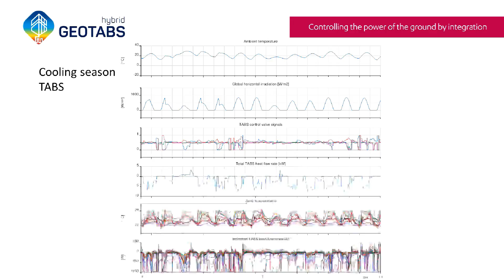Another thing that we observed at some point, but I didn't illustrate it here, is that the actual heat pump was disabled, but heat was being drawn in from the air handling unit heating coil and being put into the concrete core activation. The air entering the building was being pre-cooled. That heat was then being dumped into the concrete core activation such that it could be cooled away at a later point. These kinds of things are very interesting if we start playing around with hydronic schematics that have a large degree of flexibility. Then I really expect that we're going to see some very interesting things pop up similar to that.